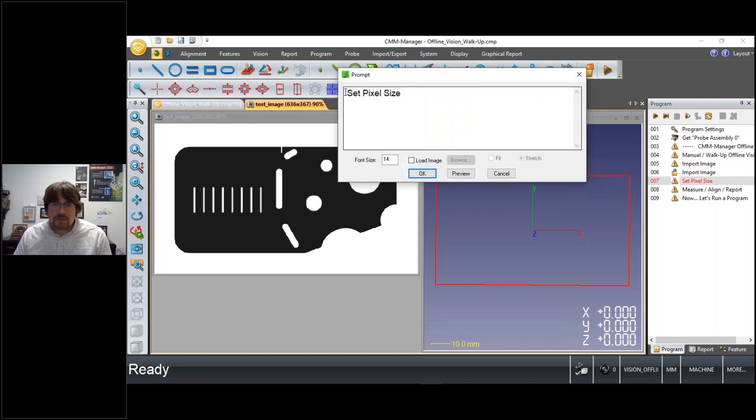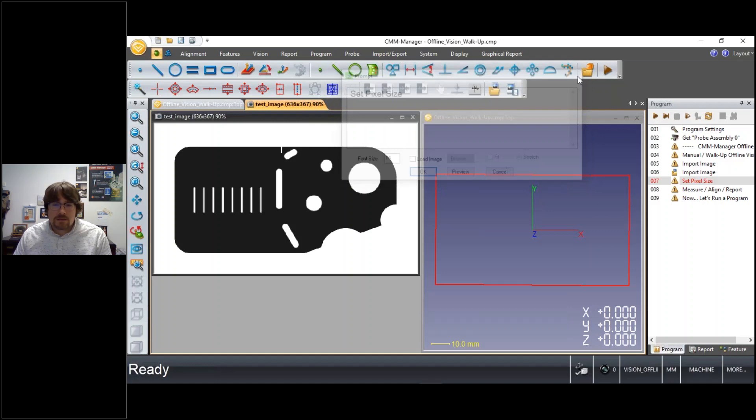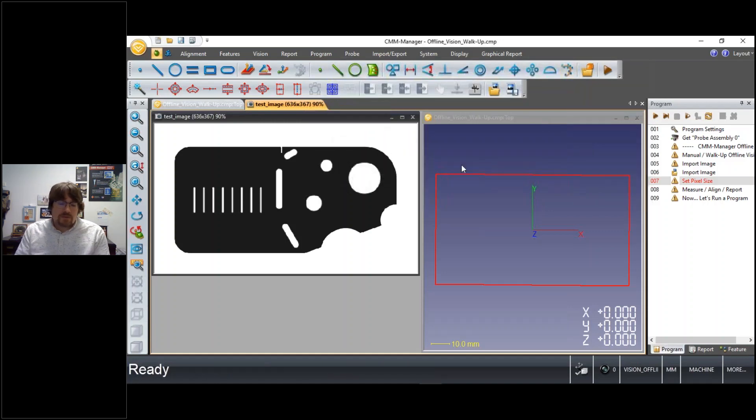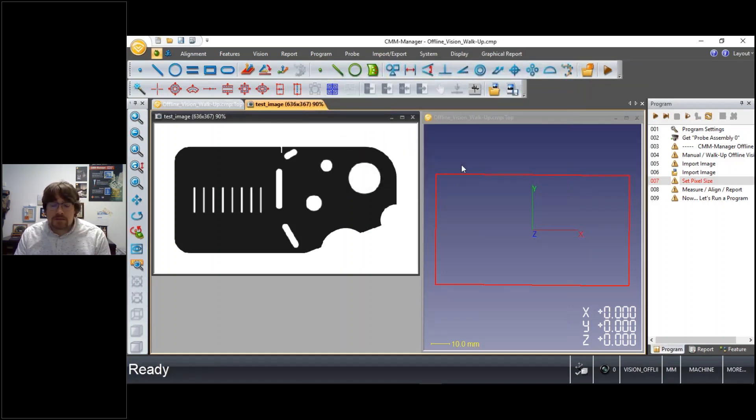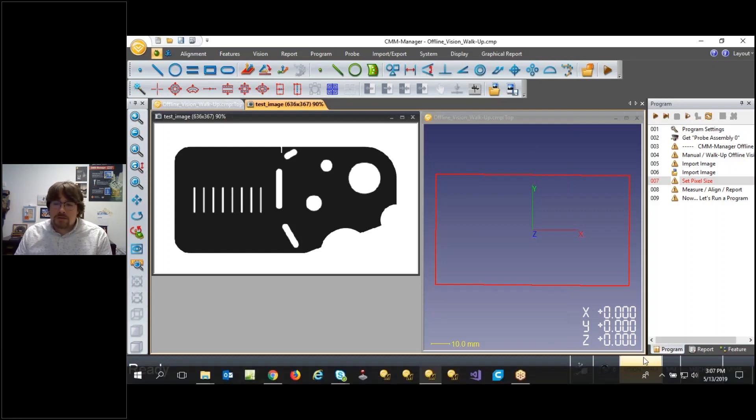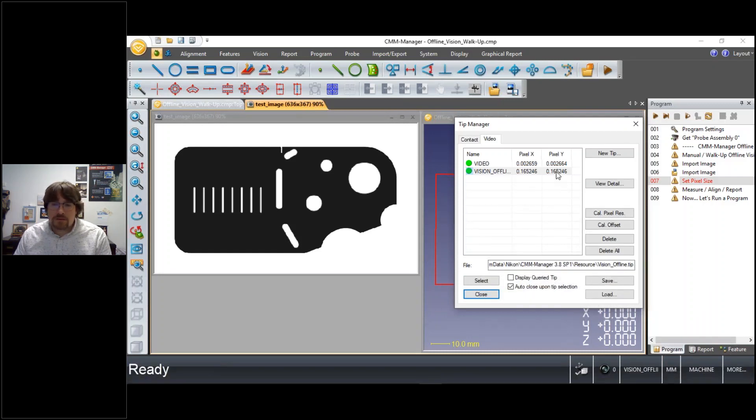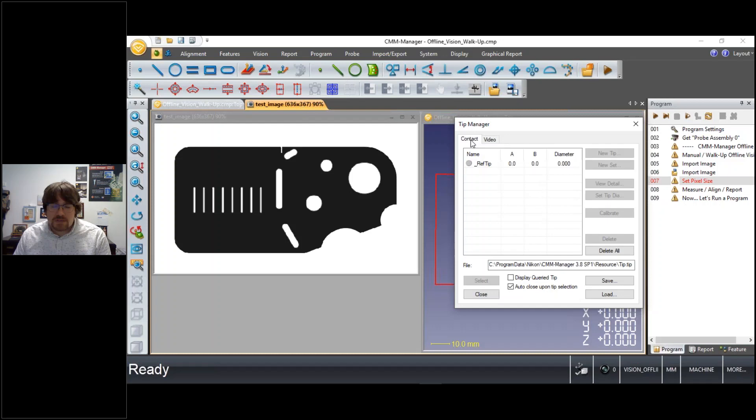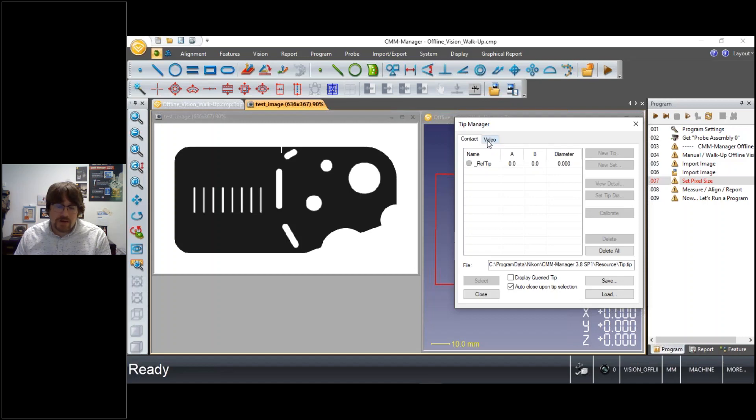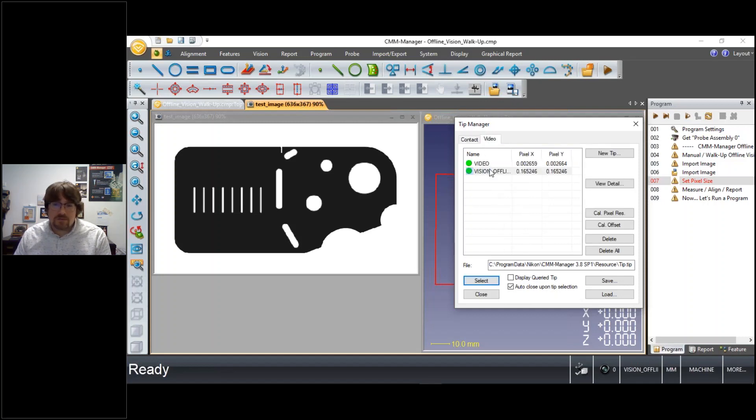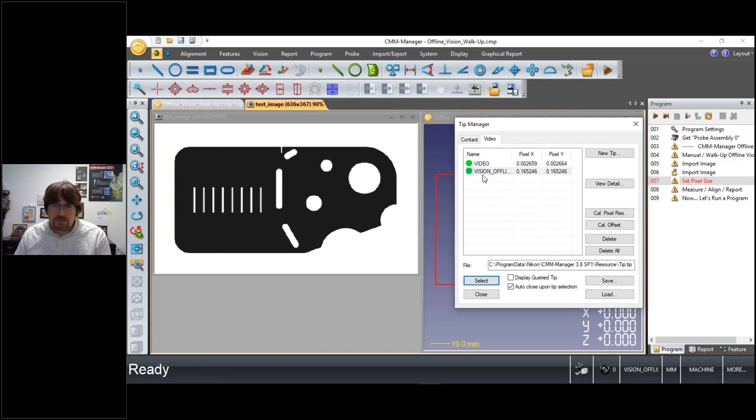So I've imported an image. Next, we need to set a pixel size. So with an online system we calibrate at least one magnification through the optics, sometimes several. That's all managed here in our Tip Manager. So if you're familiar with CMM Manager on a tactile system, you could have many different tip orientations that you're calibrating. In the same regards, you could have several video tips or sensors that you calibrate and use inside of CMM Manager.